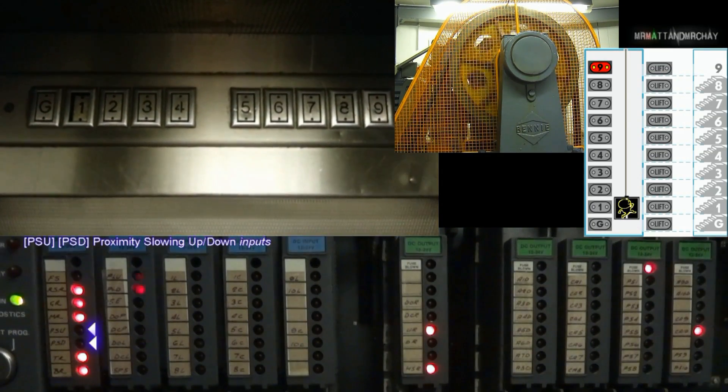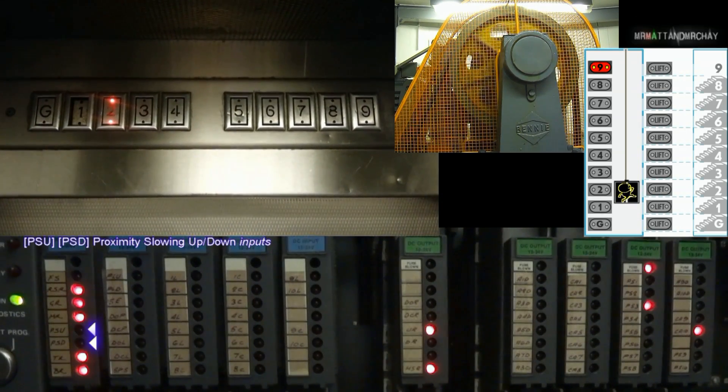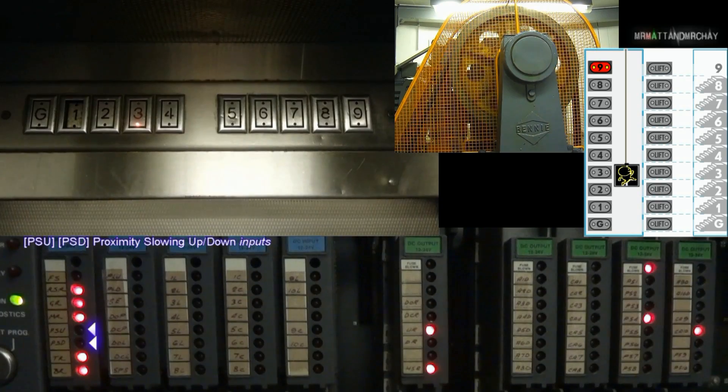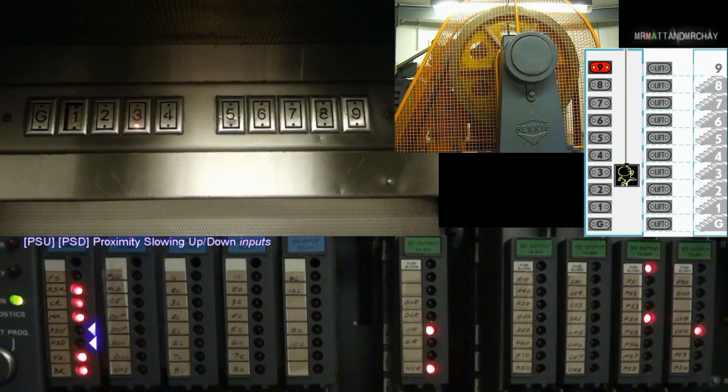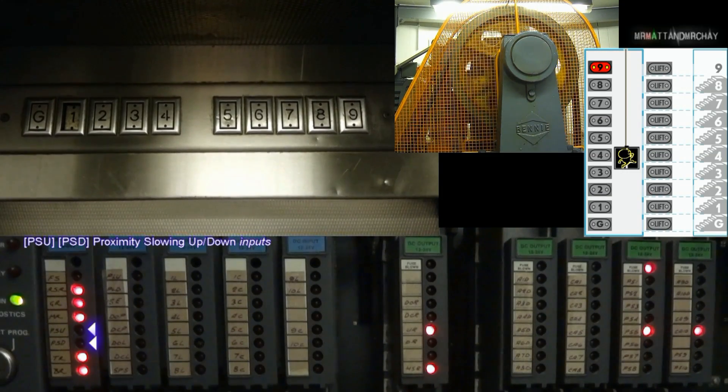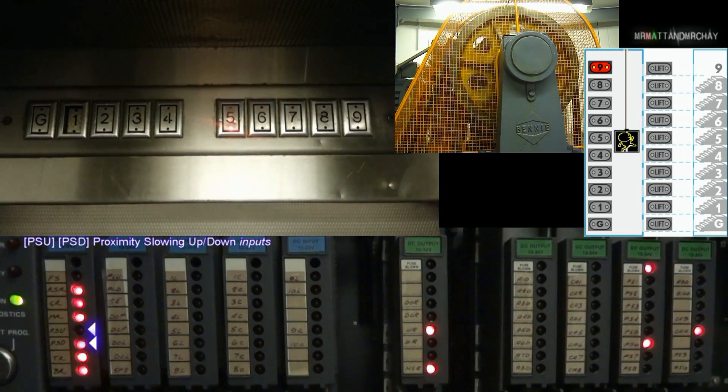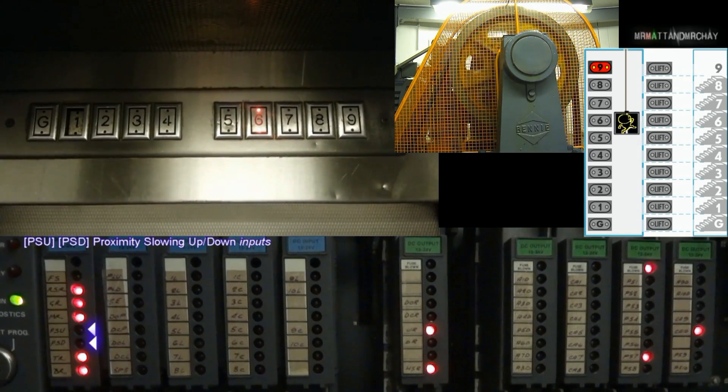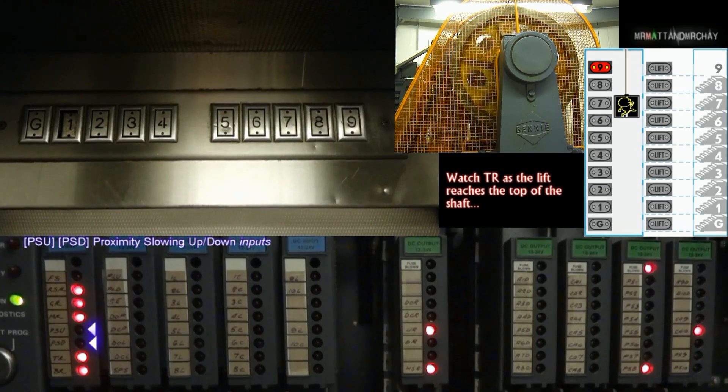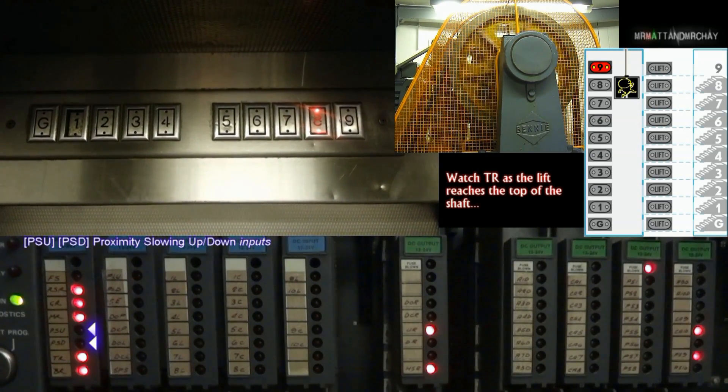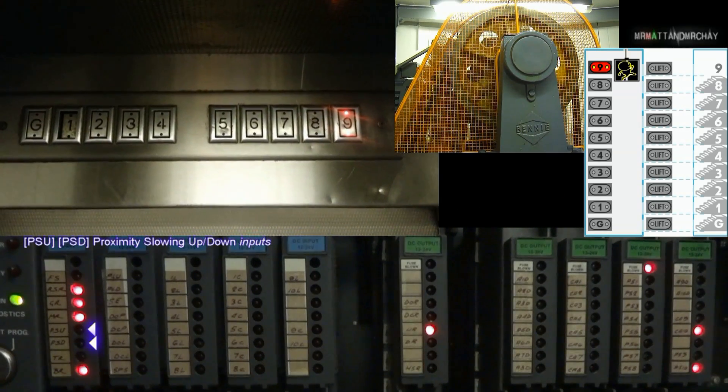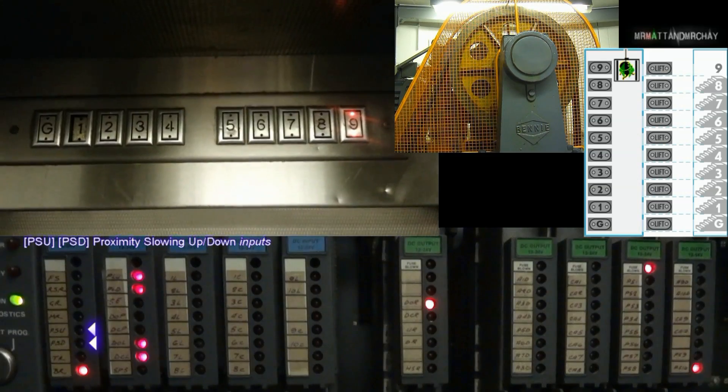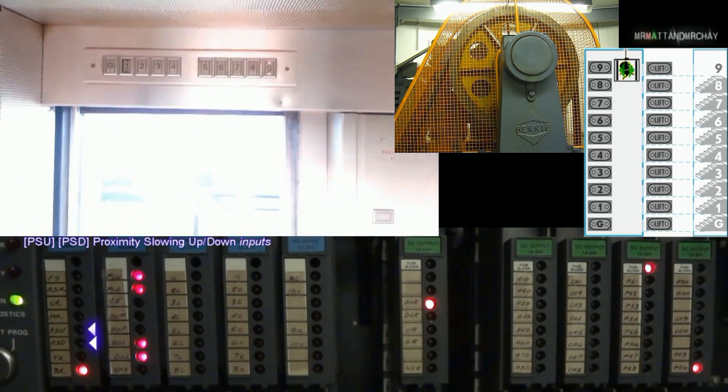PSU, slowing proximity switches. These are like magnets that are positioned between each floor, and are read by the lift car when it travels. These inputs have two purposes. First, if the lift is due to stop on the next floor, it will put the lift into slow speed, ready to arrive at the floor. Secondly, they are used to count floors for the lift's car position. If the lift is going down, the PSU magnet is passed first, followed by PSD. The controller then counts the lift down one level. It's the opposite for upwards travel.